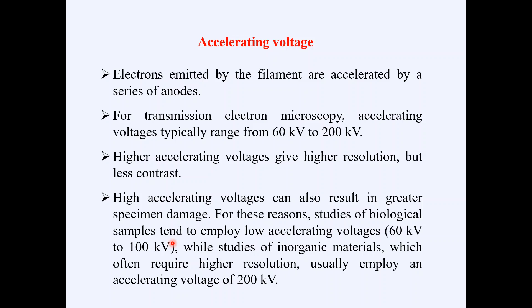For the study of biological samples inside the TEM, a voltage in the range of 60 to 100 kV is used. For inorganic materials, which often require high resolution, an accelerating voltage of up to 200 kV is normally applied. The reason for limiting voltage on organic samples is that high accelerating voltage may damage the specimen, so lower voltage is applied to protect the sample.